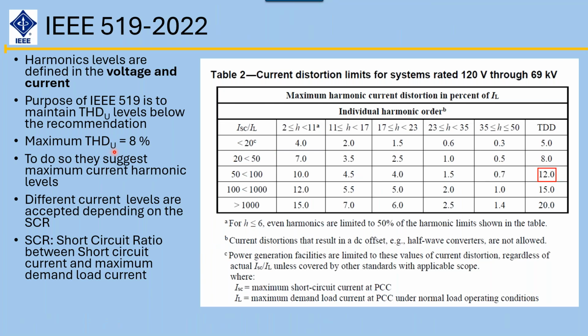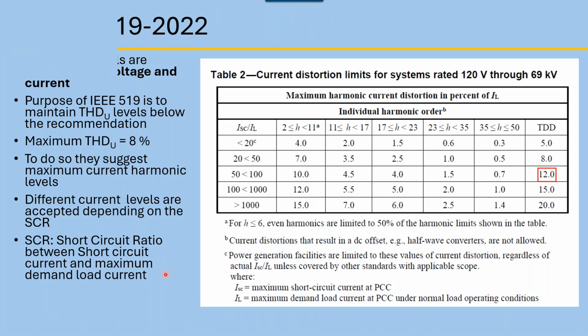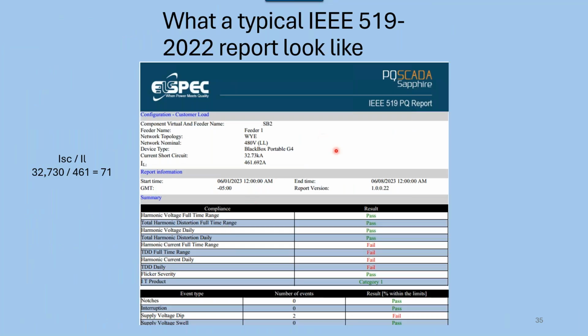Here, this THDU, U stands for voltage. That's the European nomenclature. And that was that 8% I showed in the previous slide. Okay. So here's what we've got to determine. Different harmonics have different levels that they allow per the standard. And the short circuit ratio is the difference between the short circuit current and the max current. So, any questions? In this example, I'm using the meters I use for all of my analysis, from a company called Elspec that we represent. They do a lot with power factor controls, do a great job for us. They actually use SCRs for doing it so the capacitors last forever instead of contactors switching in and out.